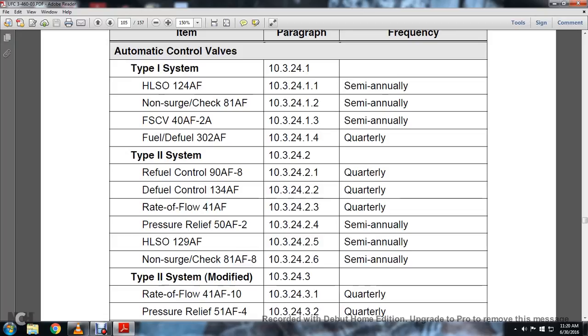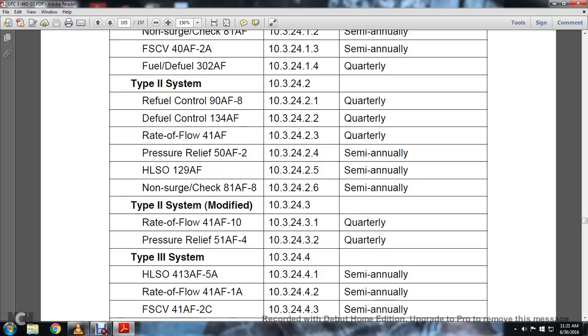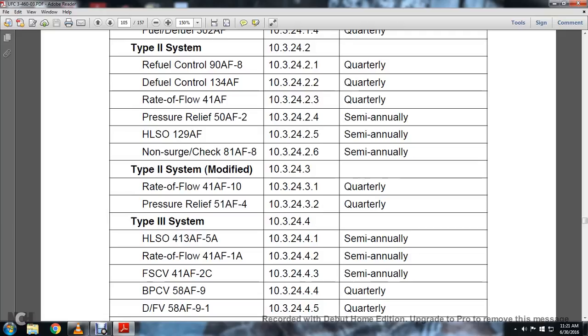The refuel control, 90 AF 8, 10.3.24.21, quarterly. Defuel control, 134 AF, 10.3.24.22, quarterly. Rate of flow, 41 AF, 10.3.24.23, quarterly. Pressure relief, 50 AF 2, 10.3.24.24, semi-annually. High level safety operation, 129 AF valve, 10.3.24.25, semi-annually. Non-surge check, 81 AF 8, 10.3.24.26, semi-annually. Type 2 system modified: rate of flow, 41 AF 10, quarterly. Pressure relief, 51 AF 4, quarterly.